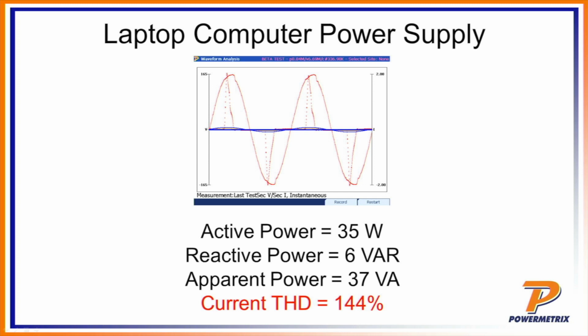Current THD is even worse than the LED bulb that we looked at earlier. Almost 150% of the energy, 1.5 times the energy being consumed over the fundamental energy being put into that system. Once again, if we look at the current waveform, you've got a really sharp peak here at every peak and trough of every sine wave.